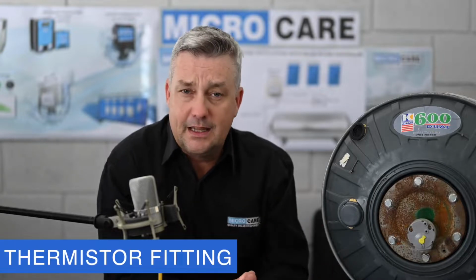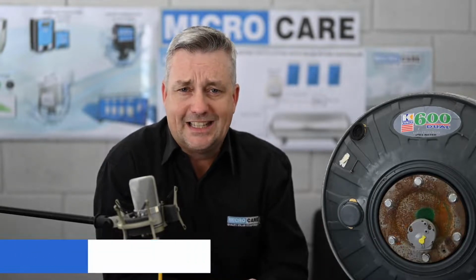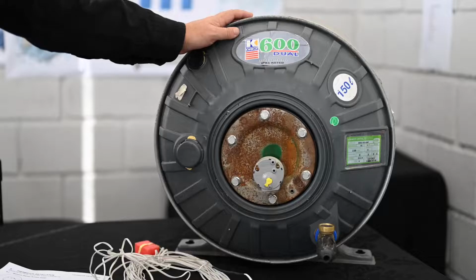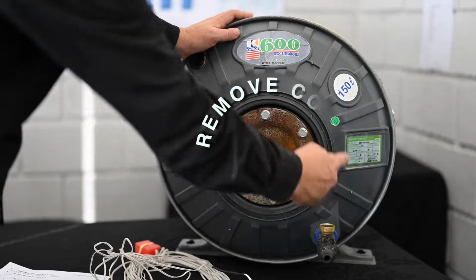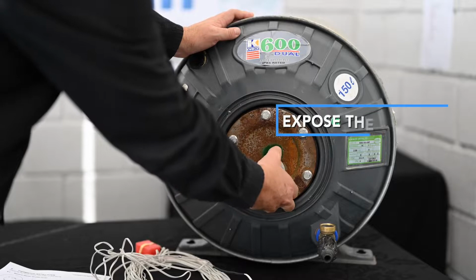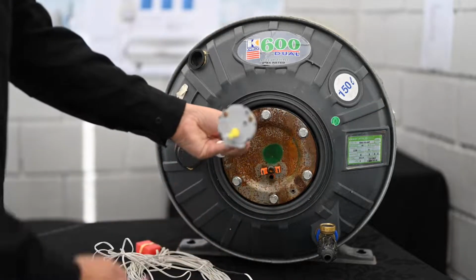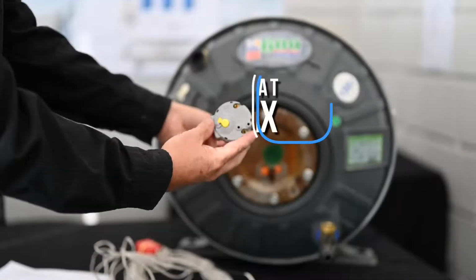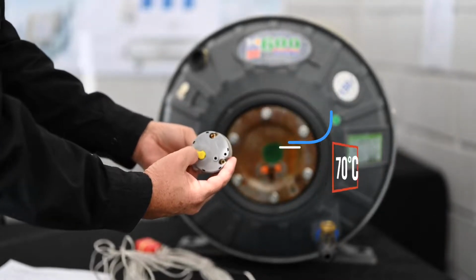Right, coming up next, we're going to look at this geyser and the thermistor and how to connect it when doing the installation. So here we have a typical geyser. I've removed the cover, the plate on the back, to expose the thermostat. I've removed it. In the back of it we can see the temperature, which needs to be set at max. In this case it would be 70 degrees.